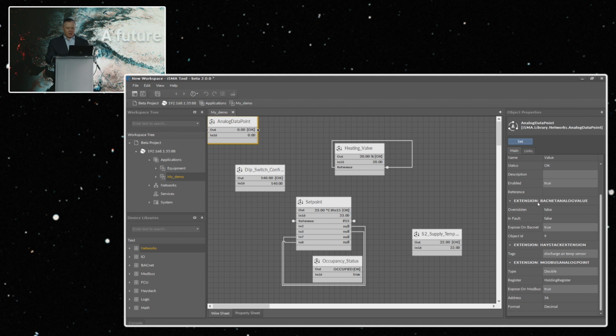For example, we've got BACnet extension, haystack extension, and Modbus extension. What this means is that once this point is added to the system, it's exposed automatically over the BACnet, Modbus, and haystack protocols. So let's do some tests.